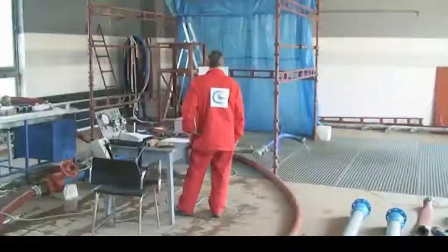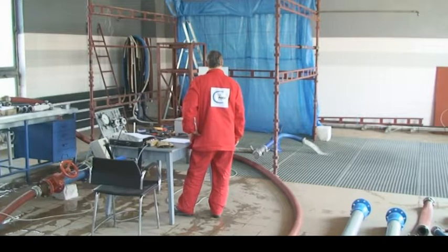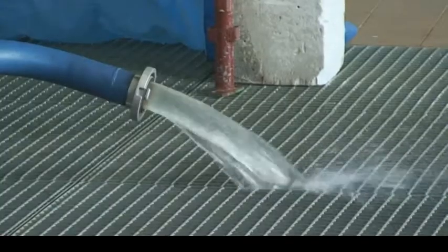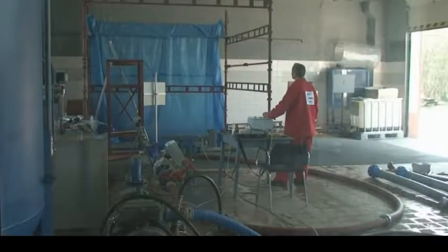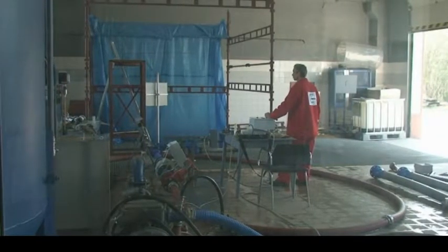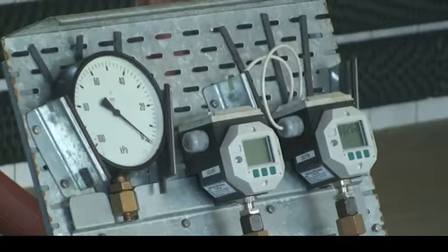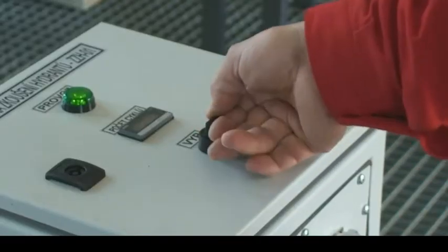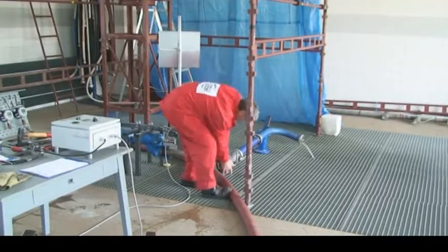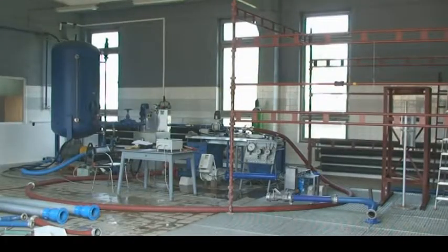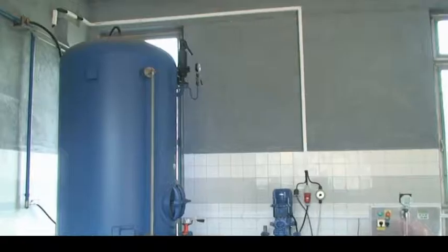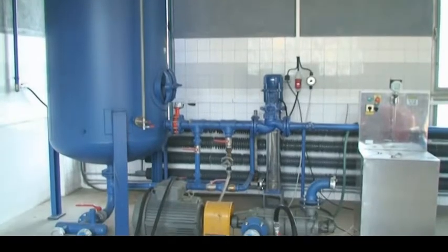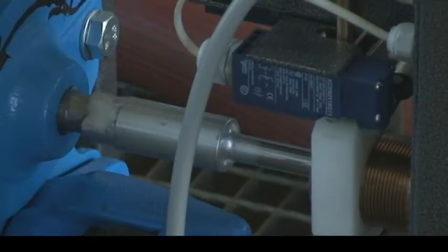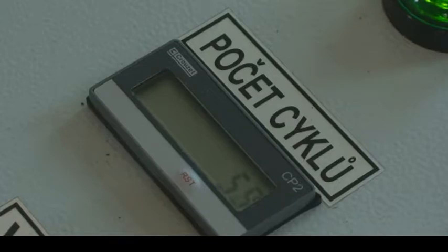Testing of technical equipment and devices for fire protection. Also, the testing laboratory of technical equipment and devices for fire protection manages the special testing equipment. On a hydraulic measuring track, it's possible to verify the flow-to-pressure relation of various components of fixed fire extinguishing equipment and of other fittings. Resistance against internal pressure, tightness and strength of components and fittings is determined by a computer-controlled pressure source, press. Functionality and durability of fire hydrants is tested by cycling.